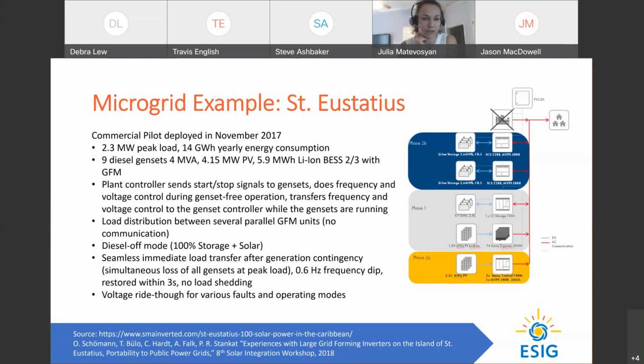There is seamless immediate load transfer after generation contingency, and they had an actual contingency on the grid with simultaneous loss of all gensets at peak load. The frequency dip was 0.6 hertz, and the frequency was restored back to normal within 3 seconds, and no load shedding happened. There have also been several real-life tests of voltage ride-through capability during various faults and operating modes. So this is a successful island application of grid-forming batteries and a 100% inverter-based grid, even though small. Next slide, please.